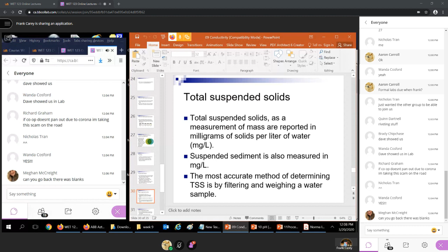So the two main ways we measure total suspended solids are gravimetric methods, and of course conductivity. So gravimetric laboratory, it takes too long. We need the quick and dirty method. But conductivity probes do not give the full picture. So newer TSS instruments use light emitters and detectors, and they're arranged in a 360-degree method. I'll be showing a video in just a bit about the new ones.